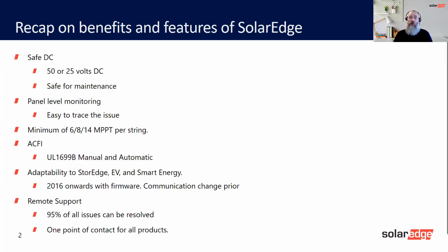The beauty of this is if you want to remove a module, if you have a faulty module, or you need to remove something for access, or maybe some extra equipment is being installed on the roof, you simply switch off the inverter, and it's incredibly safe for you to then open that string, break that string. There's no harmful voltage. The voltage is below 50 volts or 25 volts. Current is reduced, so it's safe for you to work on that roof, safe for you to do fault finding. There's no risk of high voltage or high current.